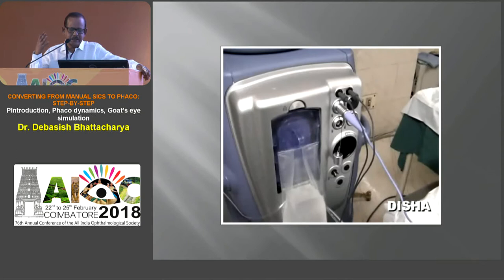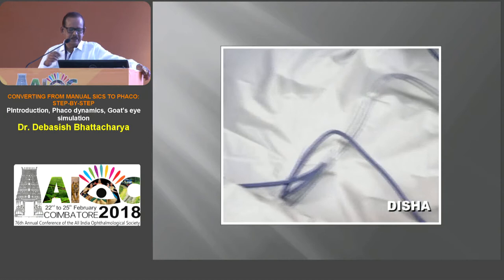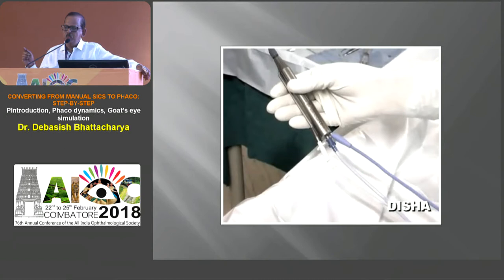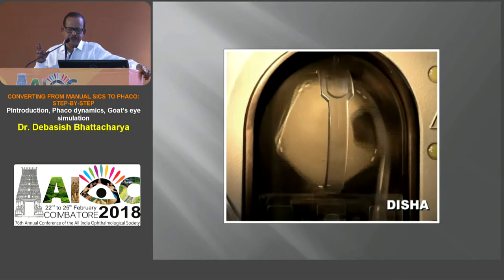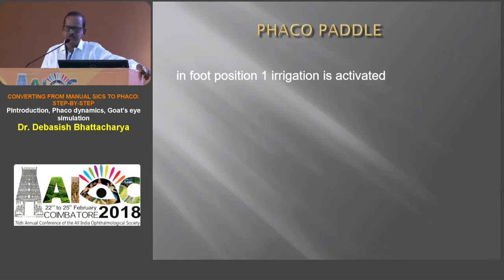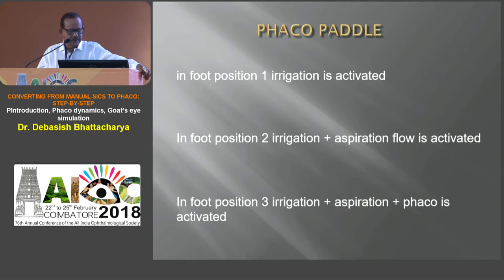Most newer machines have cassettes with a disposable vacuum sensor, which connects to irrigation and aspiration tubing down to the PHACO probe housing the piezoelectric crystals. The blue electrical connector sends signals to the piezoelectric crystals for the ultrasound to operate. The heart of the machine is a peristaltic pinching motor — the slower the aspiration flow rate is set, the slower the motor moves; the faster it is set, the faster the motor moves. This is all guided by the PHACO foot paddle: position 1 has irrigation on, position 2 adds aspiration, and position 3 activates PHACO.